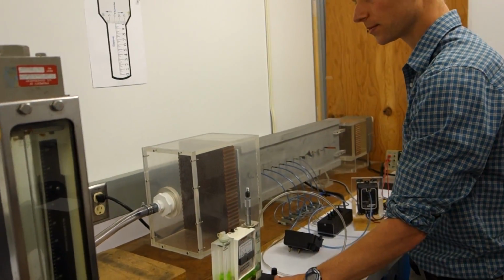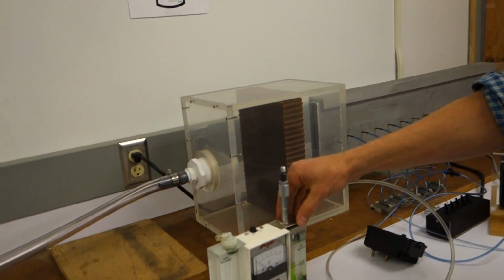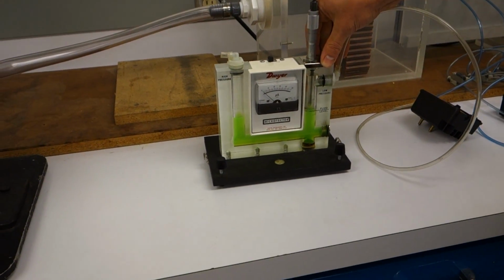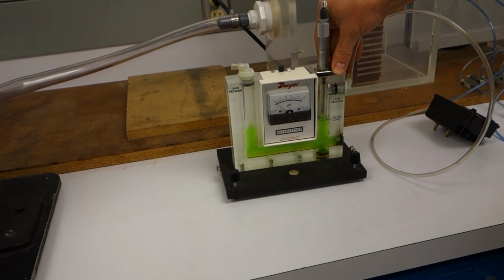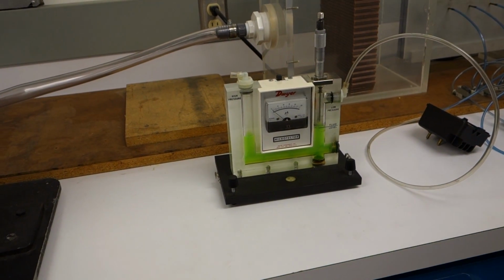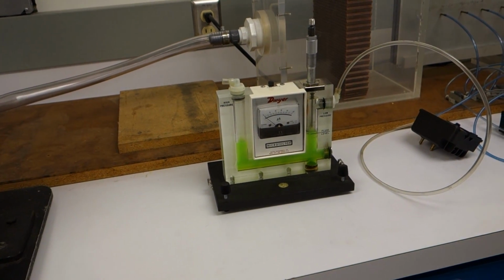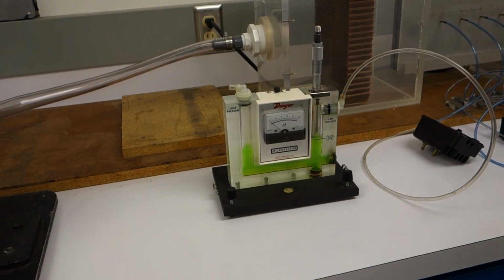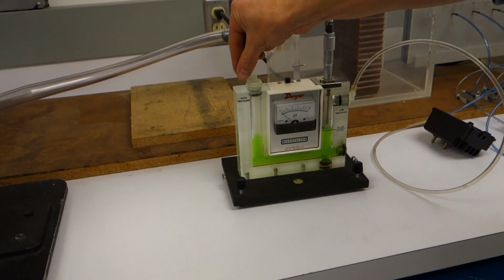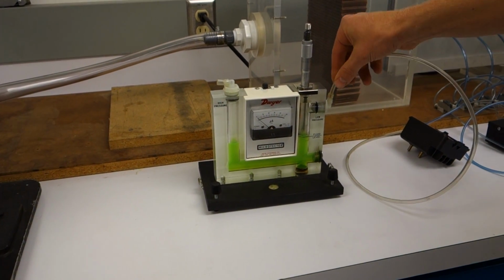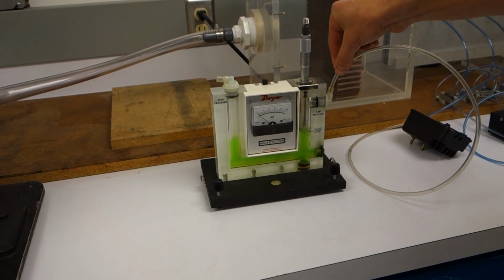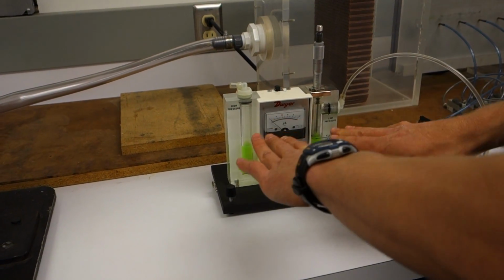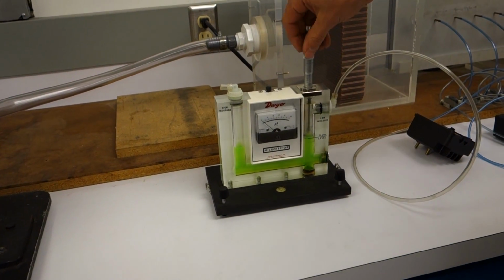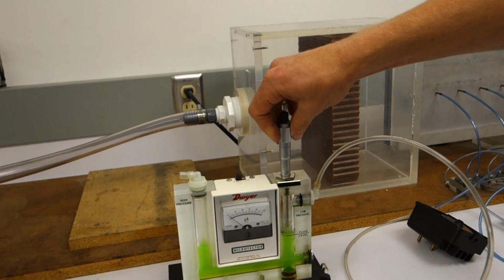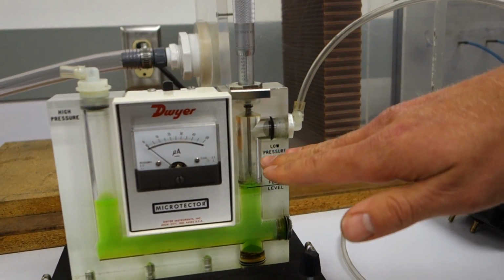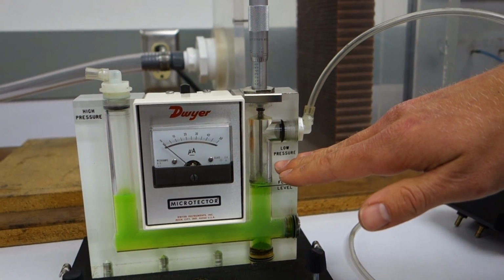All right, there's a nice green manometer here. This is an obvious pressure sensor. It's called a microtector, and we're going to be using it to calibrate our electronic pressure transducer. And the way this works is really clever. So there's two taps, one here, one here. When we apply a low pressure to this tap, the water level will rise in this direction. And you'll see there's a metal probe over here, which is screwable up and down. When the water level rises, the probe will become submerged.